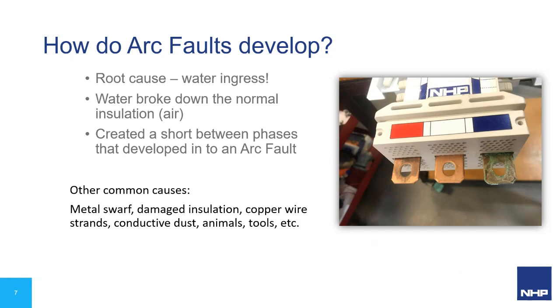As soon as we received this one, we could see some pretty clear oxidation on the tags there. Some follow-up on site discovered that there was actually water ingress into this switchboard. So basically what happened was, this was a site in Melbourne in 2019. The switchboard itself was a retrofit into an existing building, replacing an older switchboard. A section of the feeder power cable was exposed to water by other trades carrying out work on the site. So this wasn't anything known to the electrician. The electrician had done all the right things, but it was other trades that had exposed the cable and not realised that that was going to be a problem.